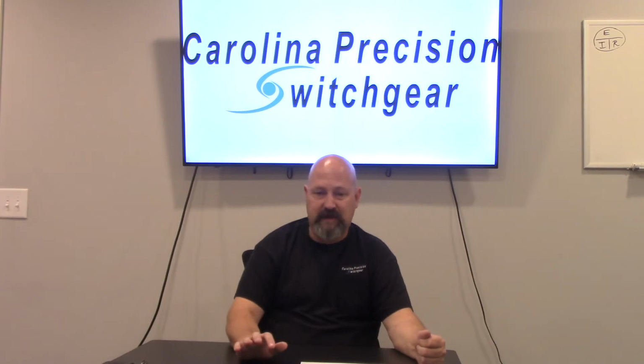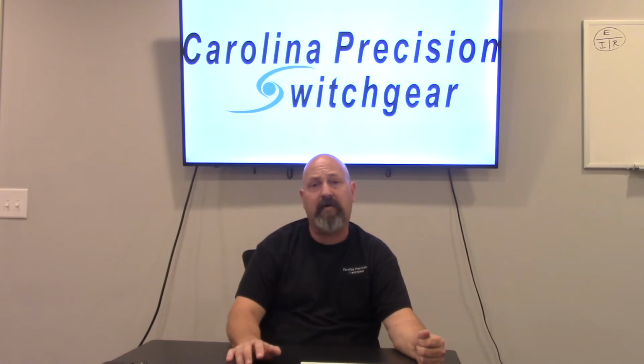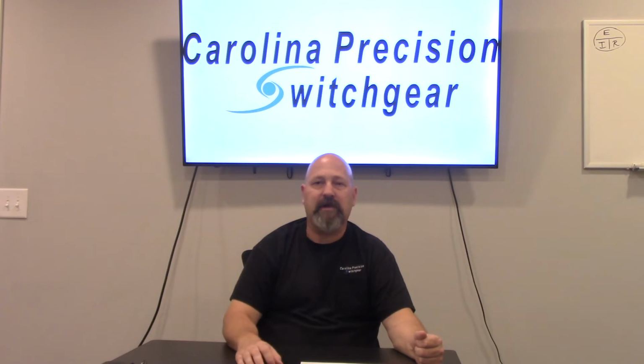First and foremost, the most important thing you need to determine is why did the circuit breaker trip? So breakers with electronic trip units will have a cause of trip indication. That will tell you whether it was a long time delay or overload, whether it was a short time or instantaneous, which are short circuit type trips, or a ground fault trip. But most important is to determine why it tripped and if the fault is isolated to prevent you from closing into a fault.